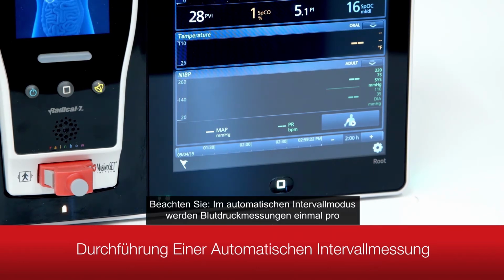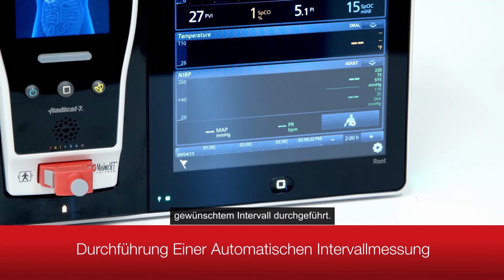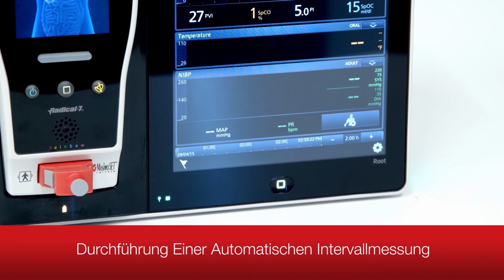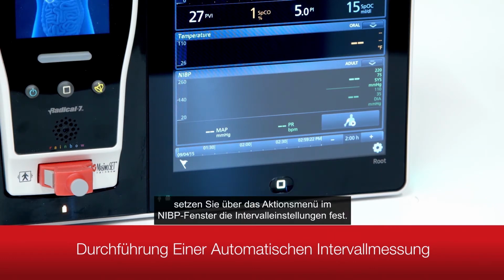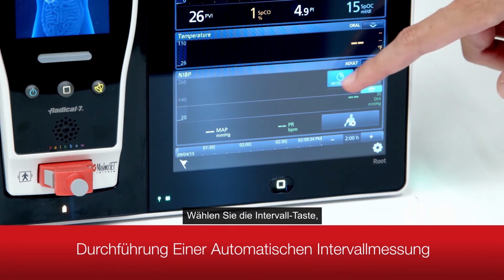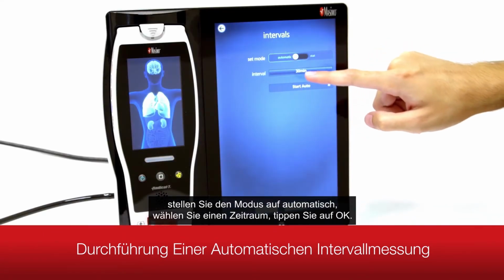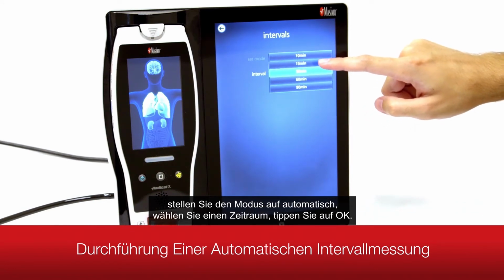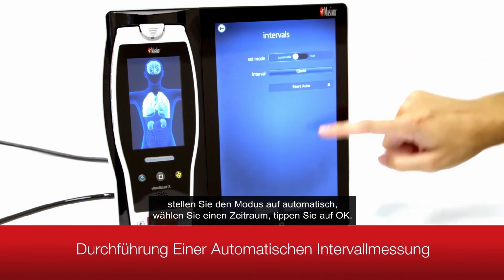Recall that the automatic interval mode will take blood pressure measurements once every desired interval. First, set your interval settings by touching the Action menu in the NIBP window. Select the Intervals button. Set the mode to Automatic, and then select the desired duration and touch OK.